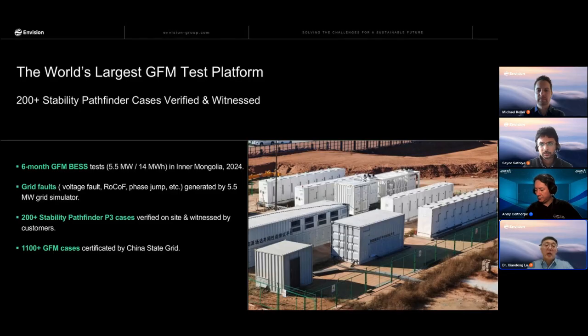We had more than 200 Stability Pathfinder cases verified on site and witnessed by some customers. We also verified the grid forming cases certified by China State Grid, more than 1,000 cases there. Although we see that the UK Pathfinder is the most advanced one in the world, in the China grid forming specification there are some even more stringent requirements, like zero voltage ride through. We do the zero voltage ride through for 10 seconds, and inject reactive current of 300%.